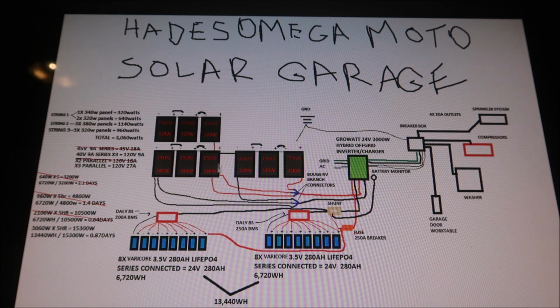So we've got the solar panels going to the inverter, and the batteries going to the inverter. The inverter is a Growatt, 24 volt, 3,000 watt inverter, so it can handle up to 3,000 watts, which is roughly, I'm guessing, around 150 amps or so. It's a hybrid off-grid inverter, guys.